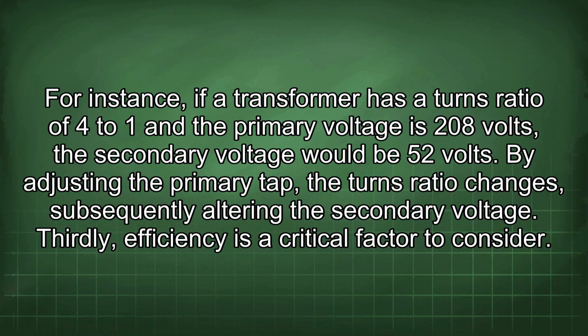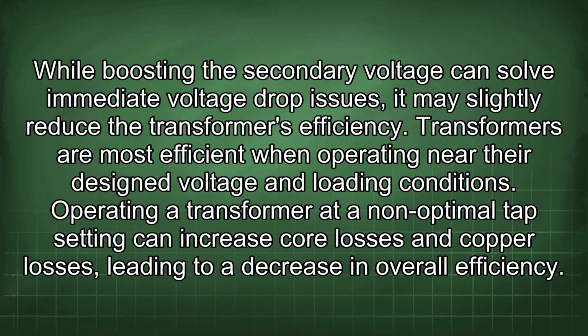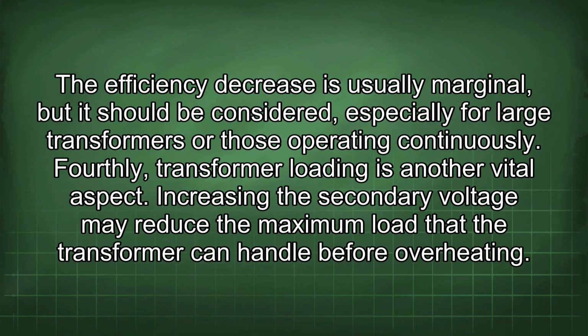Thirdly, efficiency is a critical factor to consider. While boosting the secondary voltage can solve immediate voltage drop issues, it may slightly reduce the transformer's efficiency. Transformers are most efficient when operating near their design voltage and loading conditions. Operating a transformer at a non-optimal tap setting can increase core losses and copper losses, leading to a decrease in overall efficiency. The efficiency decrease is usually marginal, but it should be considered, especially for large transformers or those operating continuously.